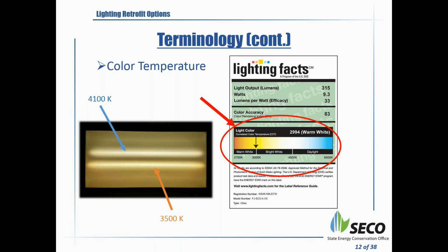The other important thing to keep in mind is that for office applications and so forth, you will normally use the 41K, or 4000 Kelvin range, but you may have special applications such as a printing room that require a higher Kelvin rating. Normally there you will see a lighting system specified with 5000 Kelvin ratings. They cost a little bit more, but that will be in printing shops and so on. So color temperature is very important, and I would like you all to keep that in mind.